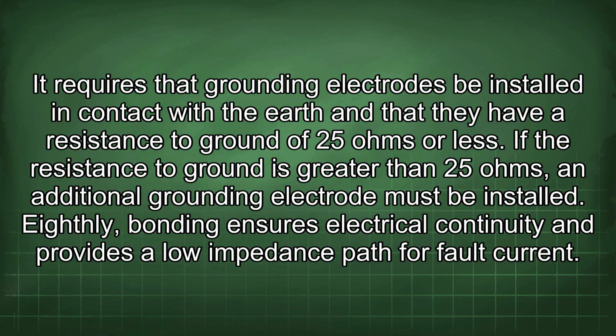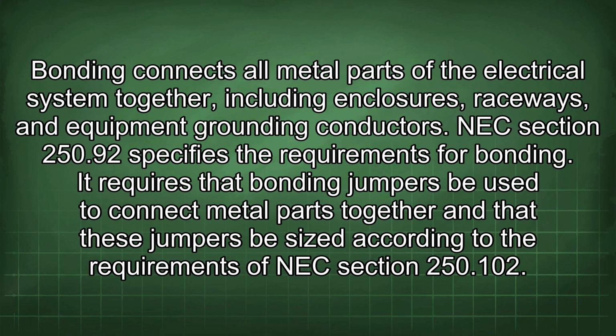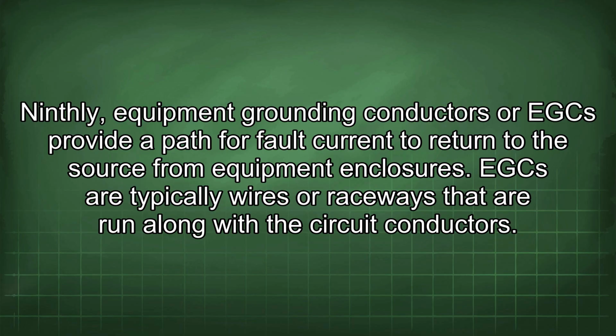Eighthly, bonding ensures electrical continuity and provides a low impedance path for fault current. Bonding connects all metal parts of the electrical system together, including enclosures, raceways, and equipment grounding conductors. NEC Section 250.92 specifies the requirements for bonding. It requires that bonding jumpers be used to connect metal parts together and that these jumpers be sized according to the requirements of NEC Section 250.102. Ninthly, equipment grounding conductors or EGC provide a path for fault current to return to the source from equipment enclosures.